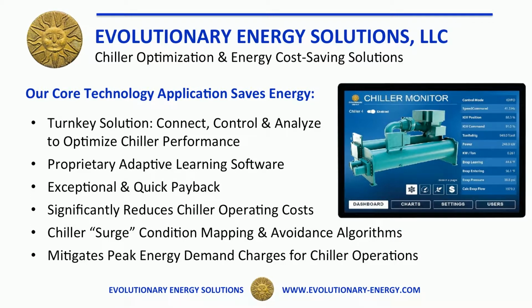But then we add something special: additional sensors on different parts of the chiller operation so we can see more about how it's operating than the original equipment manufacturers provided. With some really inventive algorithms and proprietary systems we've incorporated, we're able to make that chiller operate much smarter and reduce the amount of energy it consumes.